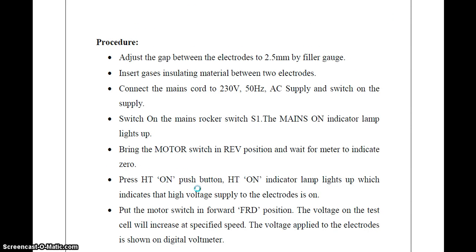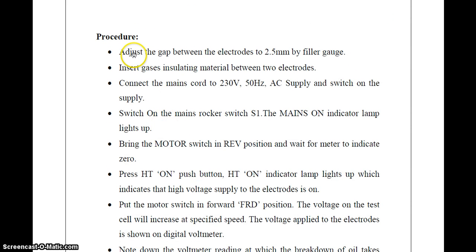Then procedure: adjust the gap between the electrodes to 2.5 mm by feeler gauge. Then insert gaseous insulating material between the two electrodes. Then connect the main cord to the 230 volt, 50 Hz AC supply given to the auto transformer or dimmer set. Then switch on the main rocker switch S1.